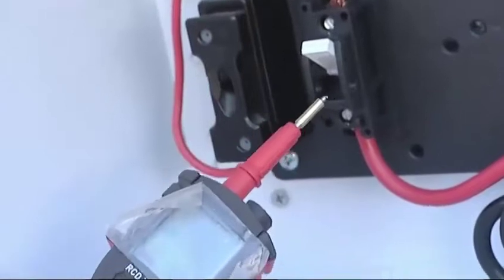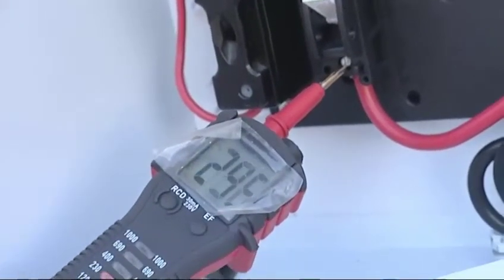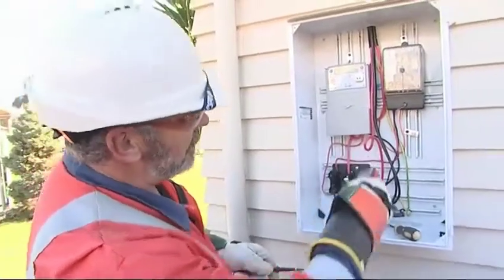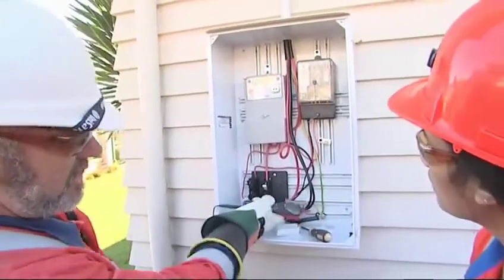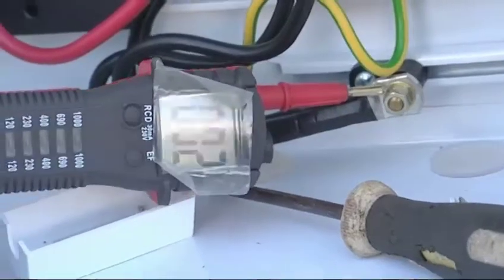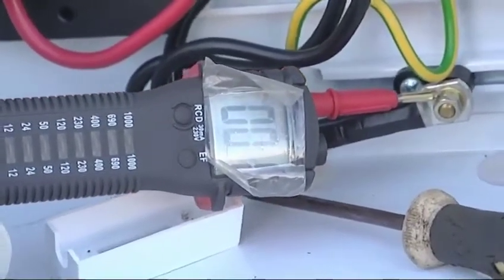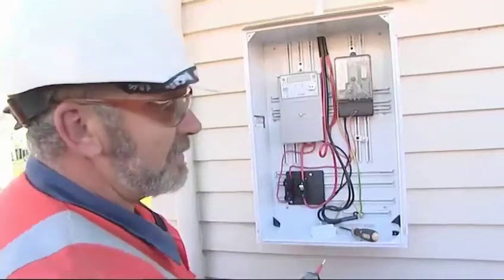We know the power is up to the bottom of the main switch, so if we touch it onto a phase, it's indicating there's more than 230 volts there. So that's all good. We then carry on through and find where the neutral comes down to a stub, and we check that. As you can see, there's no voltage on the meter, so the power's going through the phase like we want it to.